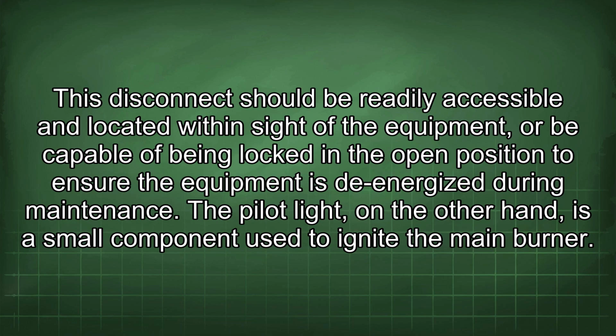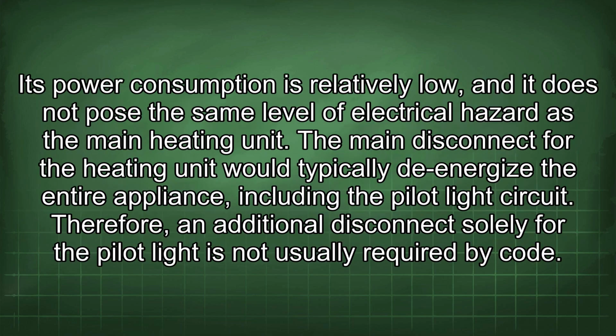The pilot light, on the other hand, is a small component used to ignite the main burner. Its power consumption is relatively low, and it does not pose the same level of electrical hazard as the main heating unit. The main disconnect for the heating unit would typically de-energize the entire appliance, including the pilot light circuit. Therefore, an additional disconnect solely for the pilot light is not usually required by code.